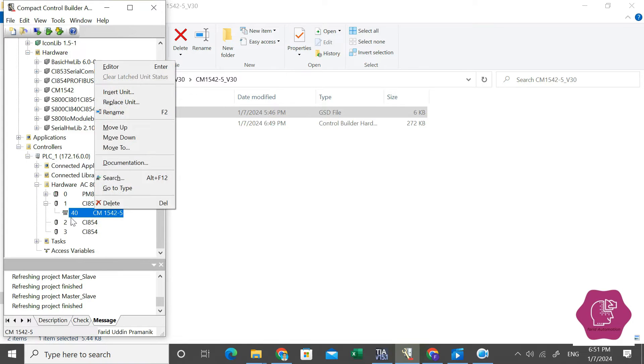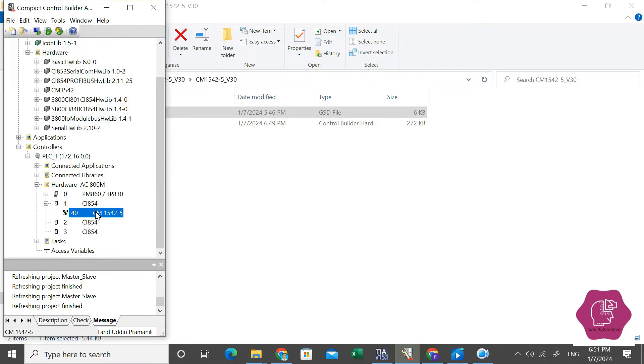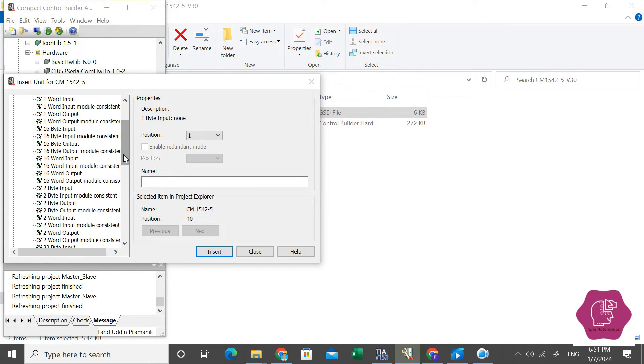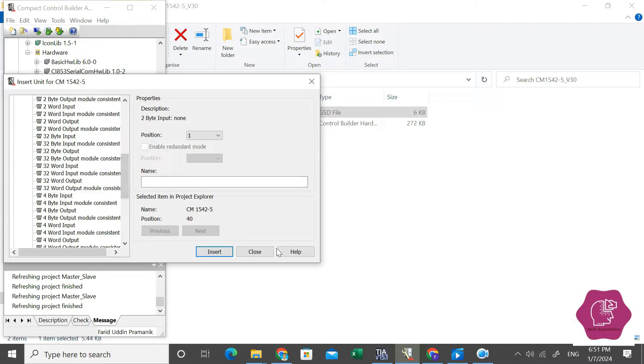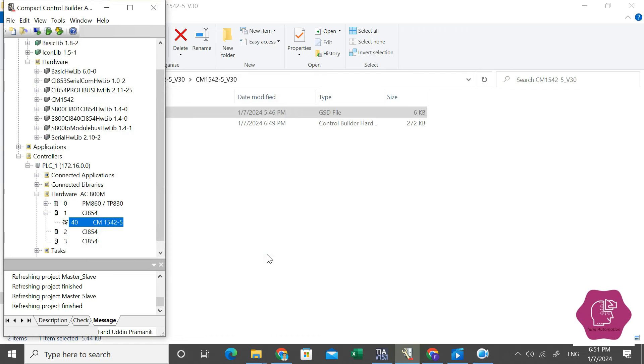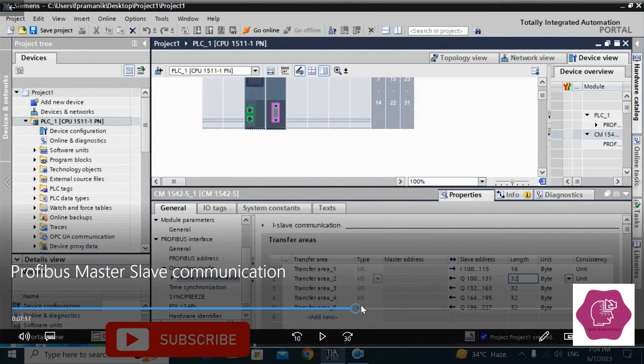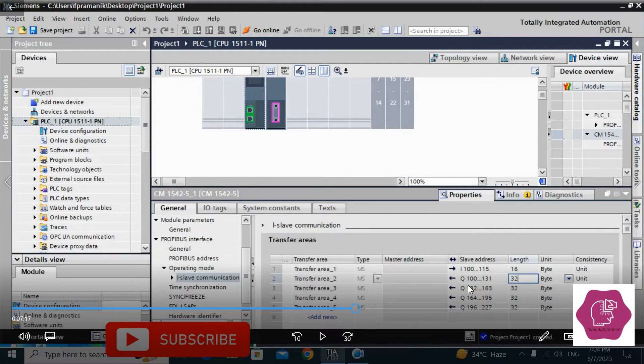So here now you have to add the module, and also how many data you want to receive and how many data you want to transmit to that Siemens PLC — that you have to add here. There are multiple options — which one you have to set, which one you have to configure, you have to select here. In Siemens we have added four. The first one is from master, meaning from ABB PLC to Siemens PLC as an input — that is 16 bytes. The other four are output from Siemens, so input in the ABB, and those are all 32 bytes.